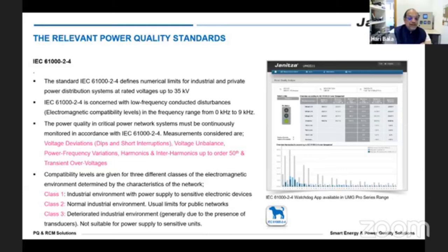So it has to be very clearly understood that 61000-2-4 is a standard which is used towards the load side, and IEEE 519 is used at the point of common coupling, which is the point of purchase of power from the distribution company by the consumers.